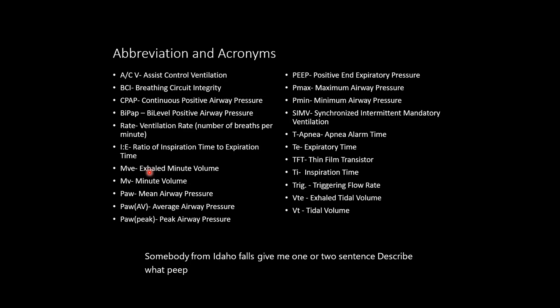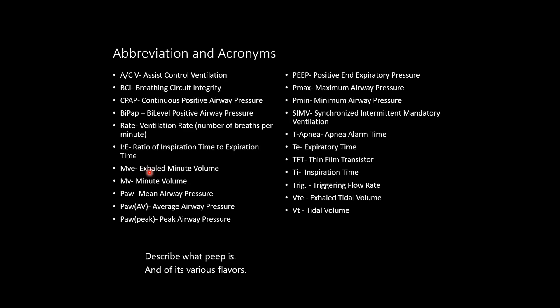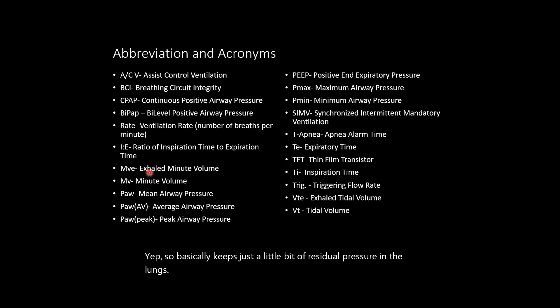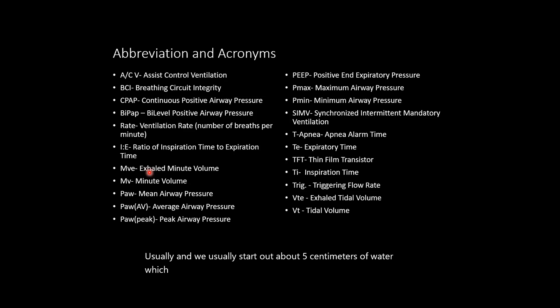PEEP. Somebody from Idaho Falls, give me 1 or 2 sentences to describe what PEEP is in all of its various flavors. So that is positive end expiratory pressure, and it just makes it so that the alveoli stay open by not allowing a certain amount of pressure to leave the body. Yep. So it basically keeps just a little bit of residual pressure in the lungs. We usually start out at about 5 centimeters of water, which in 90% of cases is not detrimental. I know we're talking a lot about intrathoracic pressure, but 5 centimeters of water is probably not detrimental. When you get above that, you start worrying about some things. When you get above 10, you really start worrying. Although in some cases, you will see PEEP levels significantly higher than that.